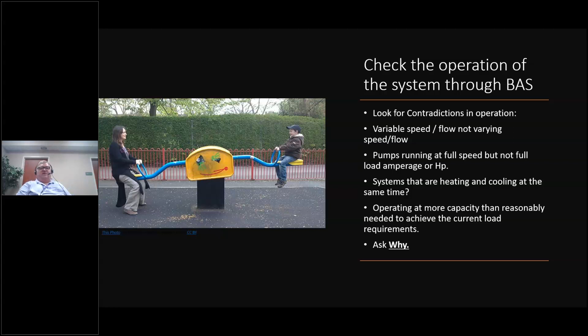I use the demonstration here. It's kind of an unbalanced seesaw. It's obvious that we're doing something here, but it's not required over there. Comparing the full speed, this is the example I give. It's 95% of the speed, 11.9 amps, but the full load amperage on the motor is quite a bit higher than that. So you have plenty of room in the motor, but it's not fully operated. At full speed, it's not fully loaded. These are things that indicate what's going on.